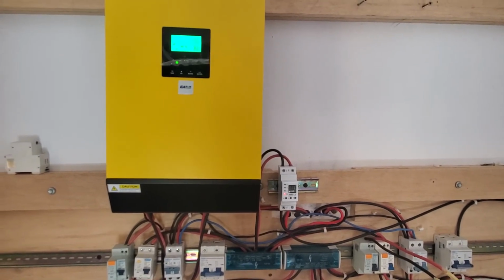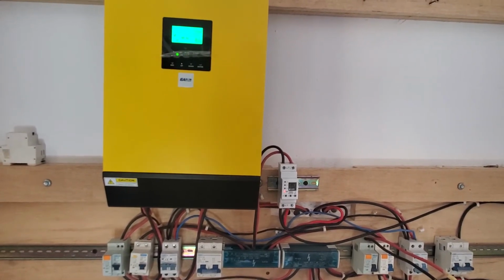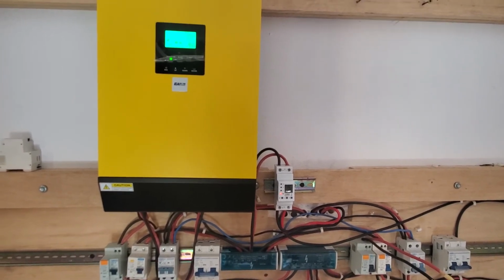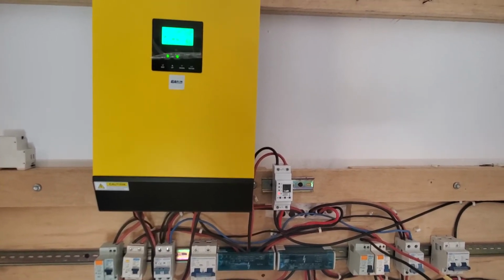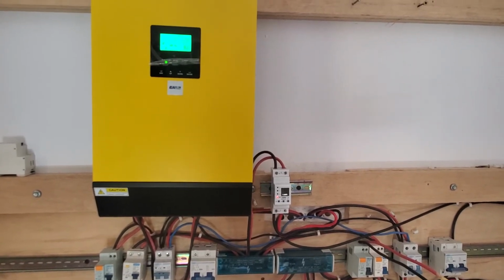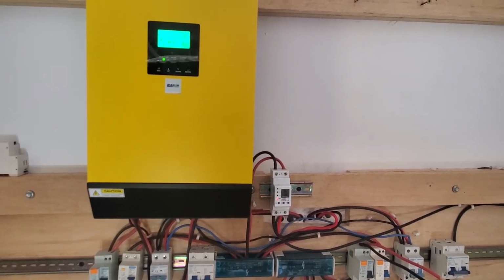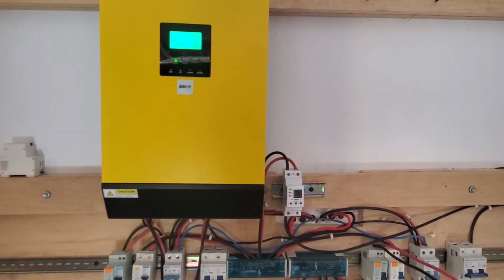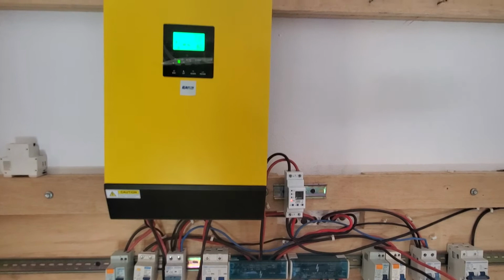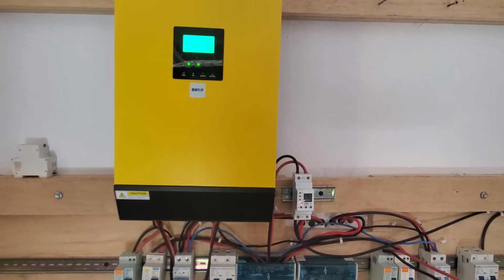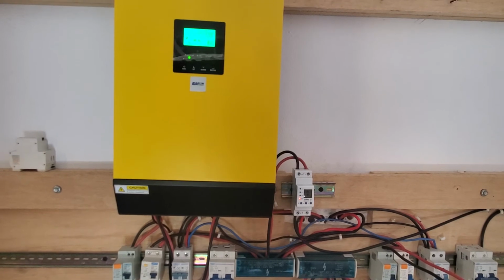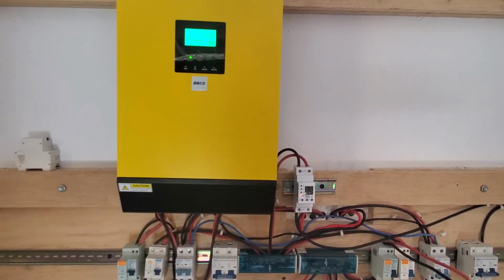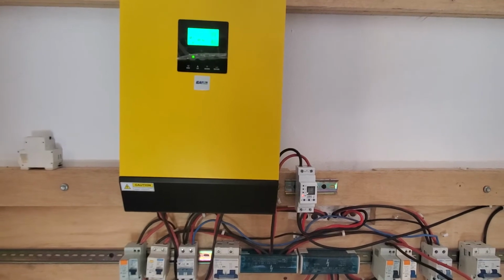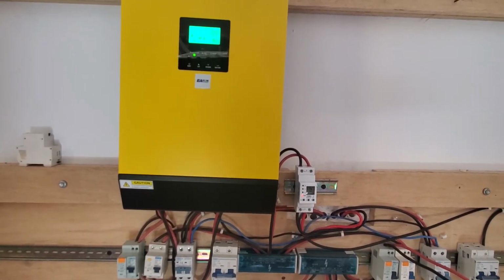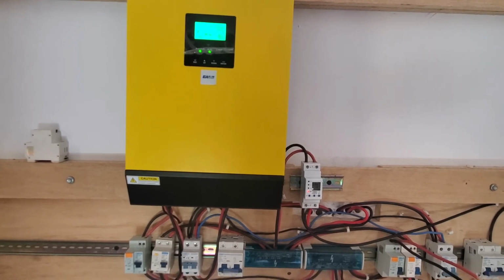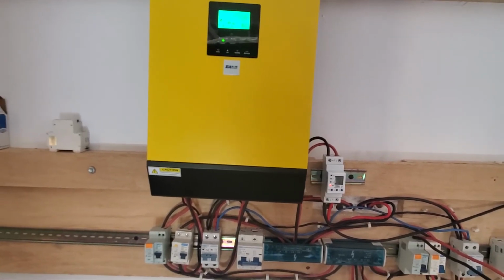Yes, the hybrid unit can be configured to run off-grid and then grid-tied, where grid-tied means that it is connected to the grid as part of its operations. So if the solar input is less than the energy required, then it's going to top up the remaining energy through grid utilization. Okay, if it is operating off-grid entirely, which means that we're going to take off the grid, then the connected load would only be powered from the solar energy.